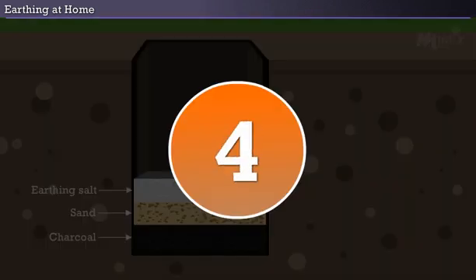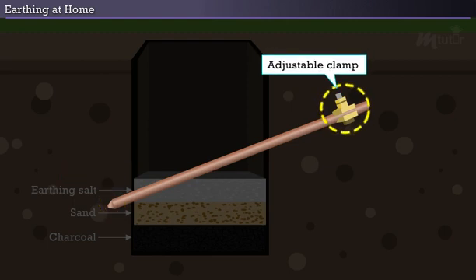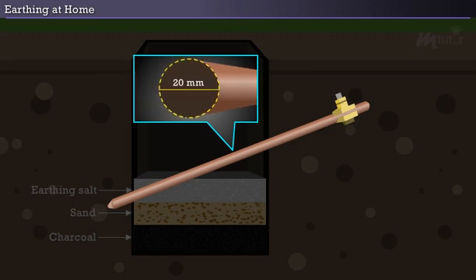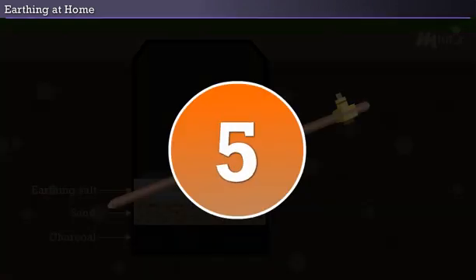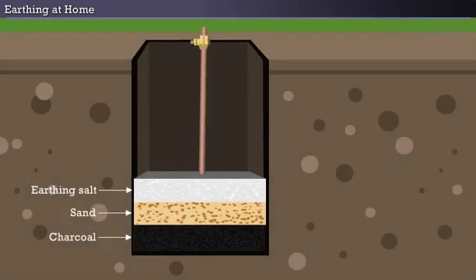Step 4: Next, take the grounding rod or earthing rod, where one end of the rod should be a conical tip. The other end of the rod should have an adjustable clamp. The diameter of the earthing rod should be 20 millimeters. The length should be 1500 millimeters. Step 5: Now, place the rod vertically inside the pit.